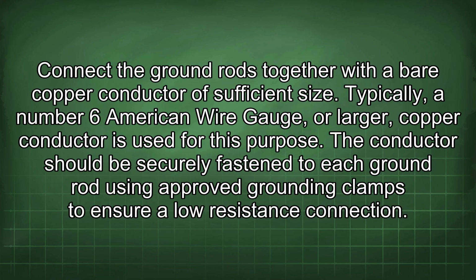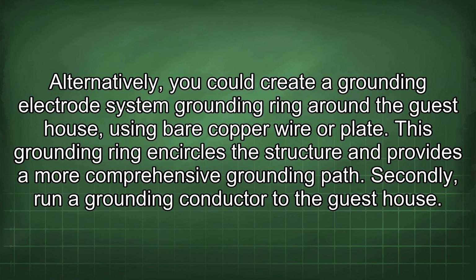Connect the ground rods together with a bare copper conductor of sufficient size. Typically, a number 6 American wire gauge or larger copper conductor is used for this purpose. The conductor should be securely fastened to each ground rod using approved grounding clamps to ensure a low resistance connection. Alternatively, you could create a grounding ring around the guest house using bare copper wire or plate. This grounding ring encircles the structure and provides a more comprehensive grounding path.